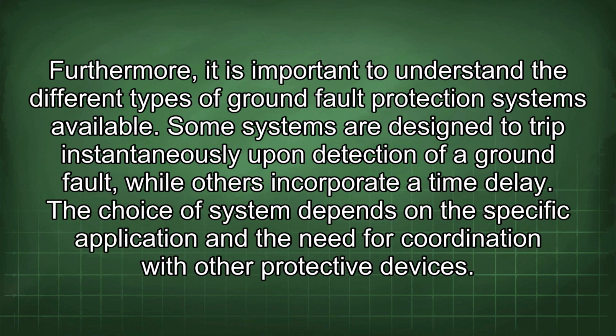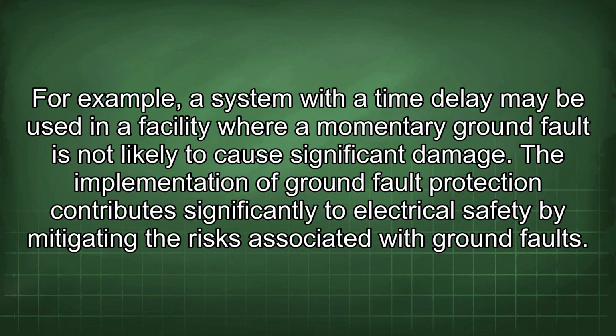Furthermore, it is important to understand the different types of ground fault protection systems available. Some systems are designed to trip instantaneously upon detection of a ground fault, while others incorporate a time delay. The choice of system depends on the specific application and the need for coordination with other protective devices. For example, a system with a time delay may be used in a facility where a momentary ground fault is not likely to cause significant damage.